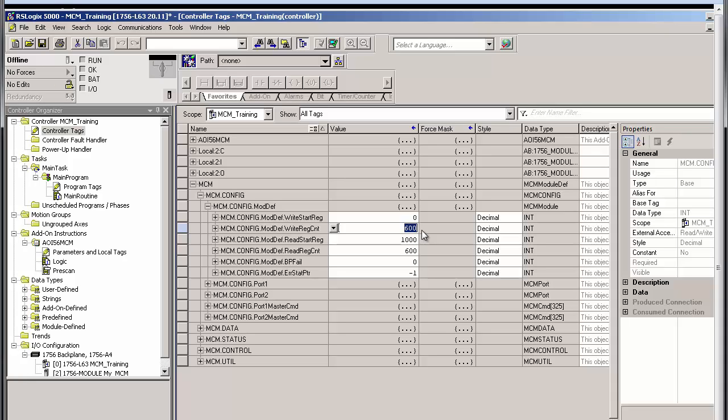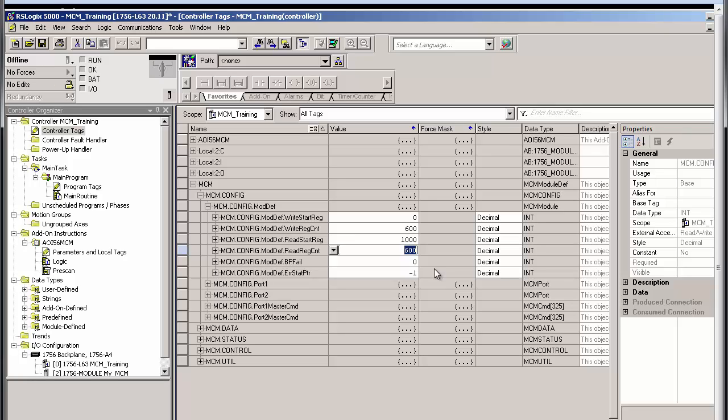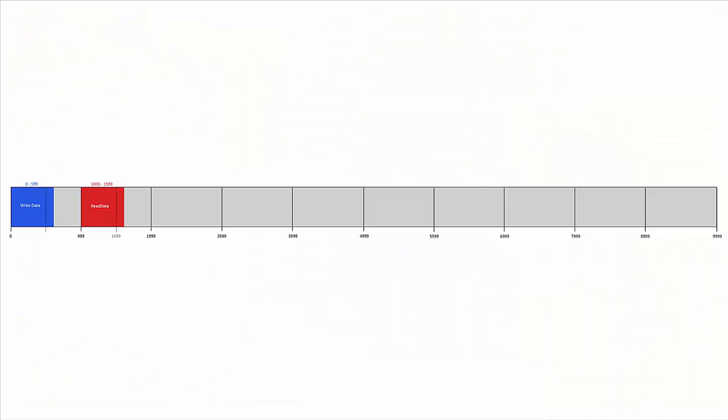I'll go down to the read-start register, and this specifies the starting register in the MCM module where data will be transferred from the network to the module and then sent on to the processor. In this case, the read registers will begin at 1,000. And the read register count defines the total number of registers the MCM will write to the ControlLogix CPU. Again, the count is set here to 600 registers. So with this configuration, the database would look something like this.